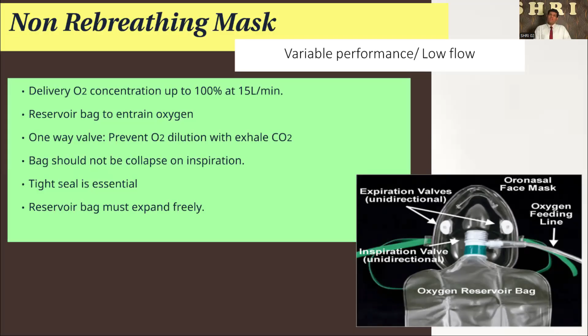So we can deliver nearly 100%, but it is not practically 100% because there is some degree of mixing of the expiratory gases in the upper respiratory tract. But at the face level, we can give 100% oxygen to the patient. And it has a one-way valve that minimizes the mixing of inspiratory and expiratory gases. And you should always have a tight seal. It's very cost effective if you want to give a very high level of FiO2 to a person.